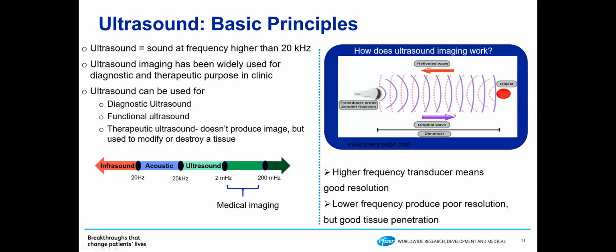So when you look at this schematic, you have a transducer which produces ultrasound at certain frequencies, and those ultrasounds travel through and hit any object, whether it's an animal or a non-live object. After hitting that, it reflects back, and the differences in the frequency and also the speed of the reflected waves can be detected by this transducer probe. And based on those differences, the equipment is able to convert them into an electrical signal and generate 2D images based on those reflected waves.